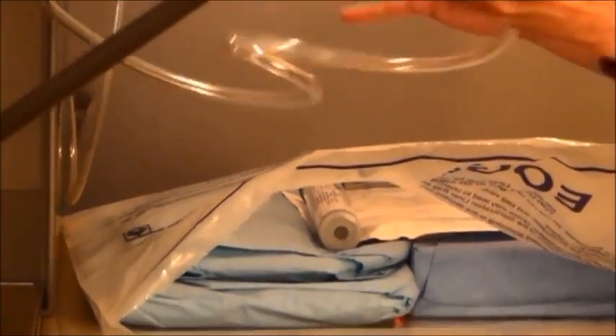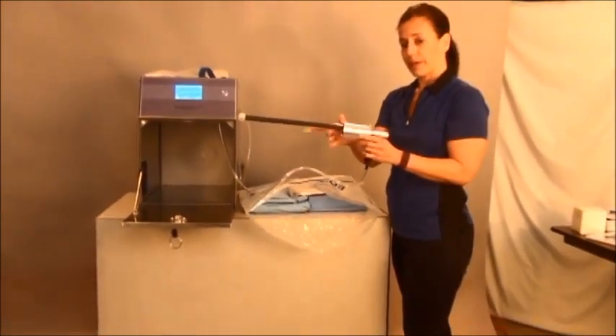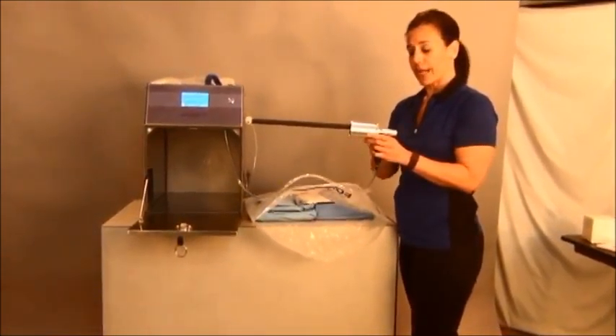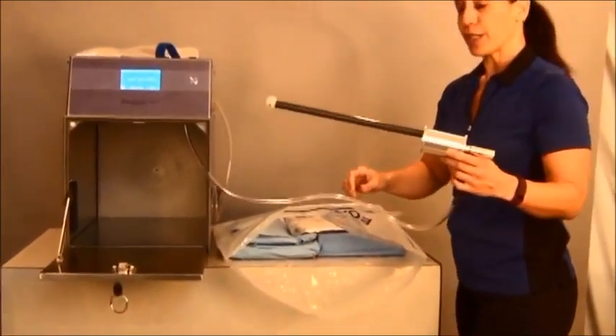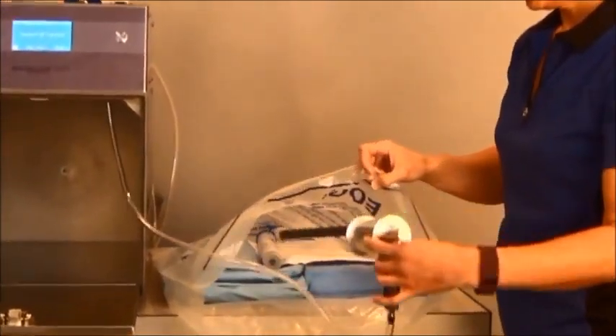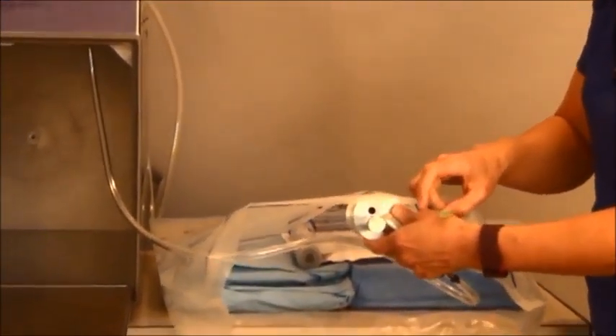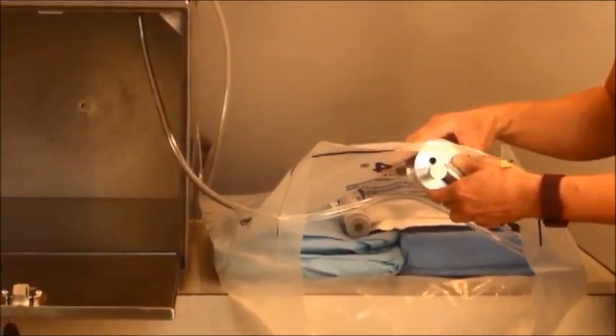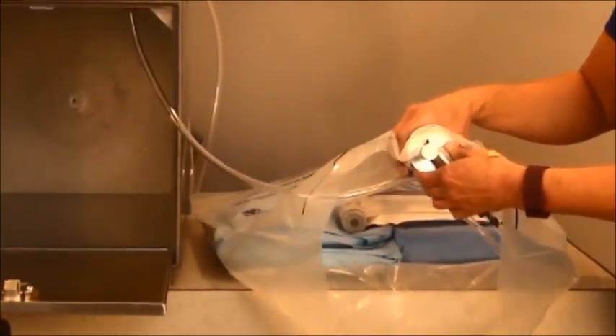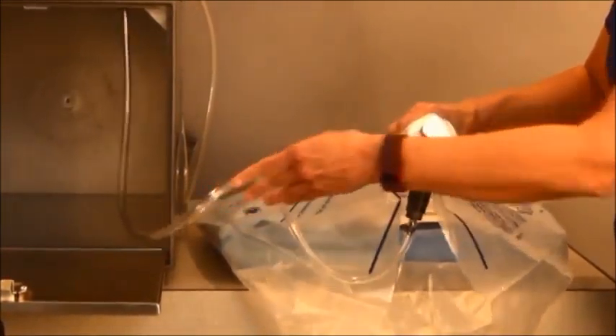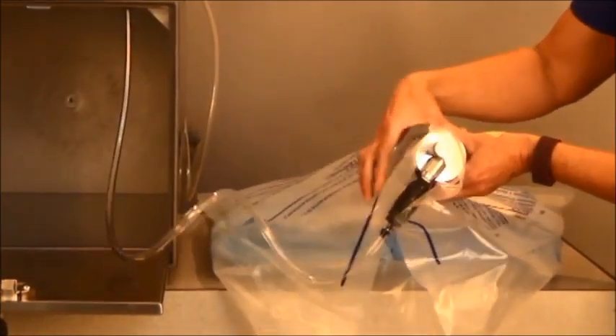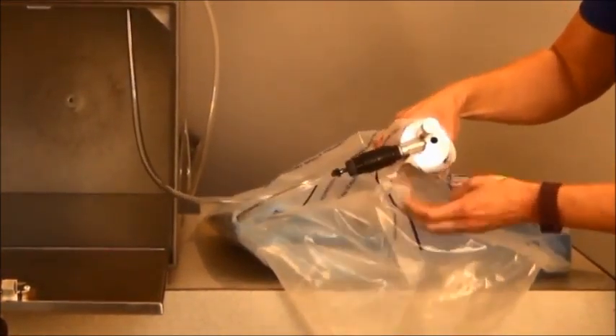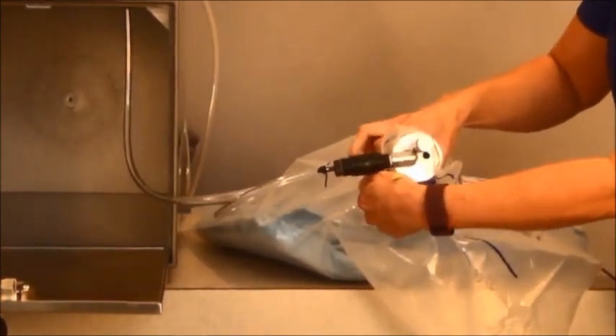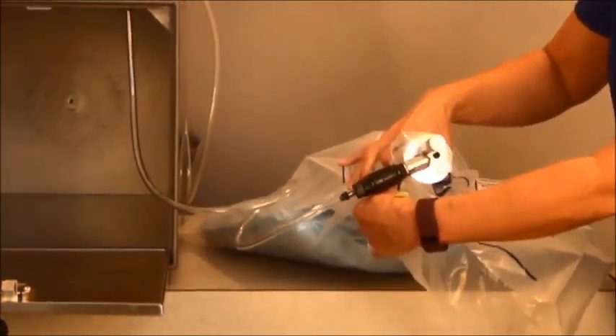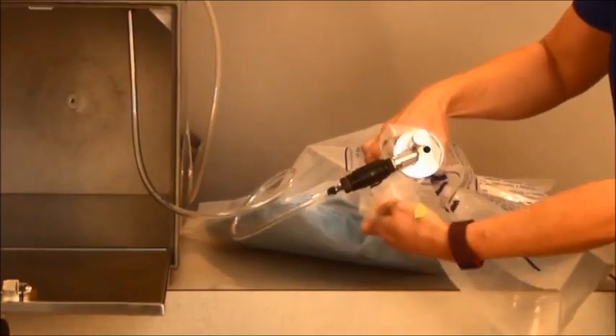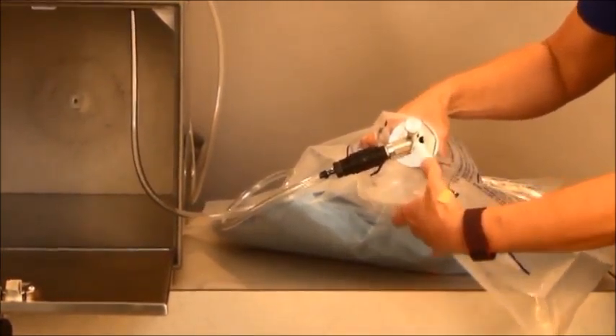Finally, you put in your purge probe. There is a silver bobbin located around the top that you can use as a guide. You want to put the purge probe at least 4 inches down into the liner bag and gather the liner bag securely around the silver bobbin. You want to make sure that there are no gaps in the liner bag to allow the ethylene oxide to escape.